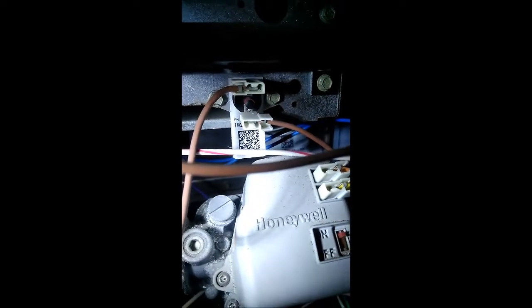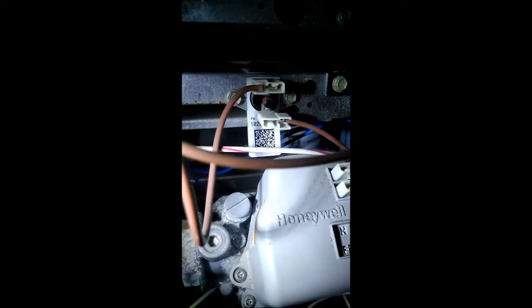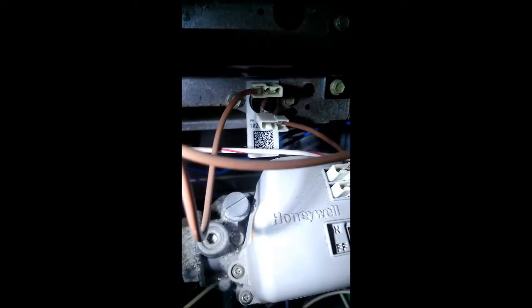Up here, this big metal plate at the top, this is your burner. This is where your fire comes from. Your gas valve goes through there and up into this burner section here, and it fires all these flames into the heat exchanger. You'll notice that right here at the top there's a switch with 2 contacts attached to it, and then that goes over here and there's another switch with 2 contacts on it, and these are your rollout switches, and they detect flame or absence of flame.